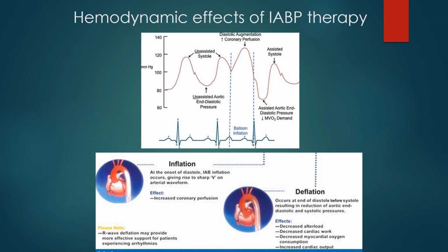Yeah, systole. That's your contraction. Duh, stupid me. Okay, I see what I did wrong. I was right. This is your systole, this is your diastole, dicrotic notch. This is where the valves are closing, right? So when the valve closes, the balloon inflates, and that's what this represents right here. And right here is the beginning of that dicrotic notch again, right before we have our balloon deflation.